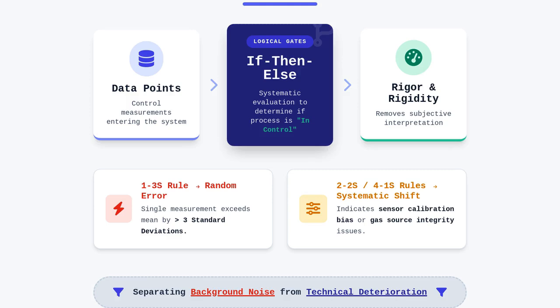Conversely, rules like 2-2s or 4-1s are designed to detect systematic shifts that indicate a bias in your sensor calibration or gas source integrity. By applying these rules systematically, you avoid the subjective interpretation that often leads to inconsistent laboratory performance. This methodology forces you to categorize deviations correctly, separating simple background noise from genuine technical deterioration.